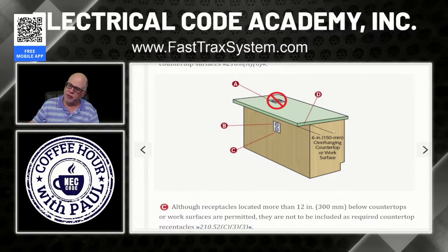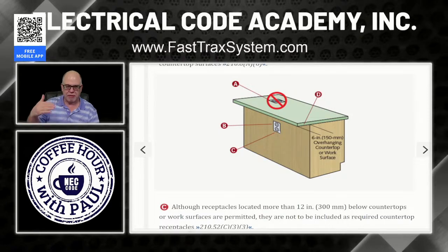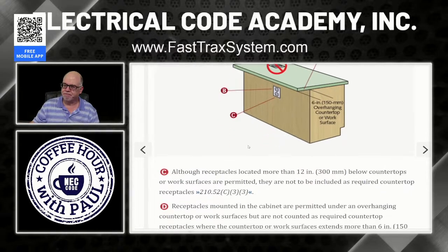Now, they could have put it here on the side. If this overhang was more than 6 inches, then you just stick it over here on the side. But every part of this receptacle can't be more than 12 inches below the countertop surface. Okay? So here you go.